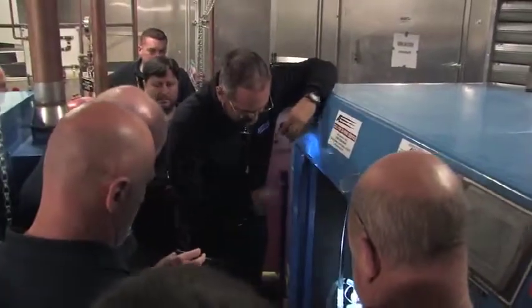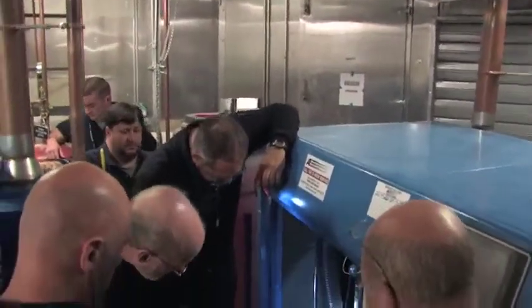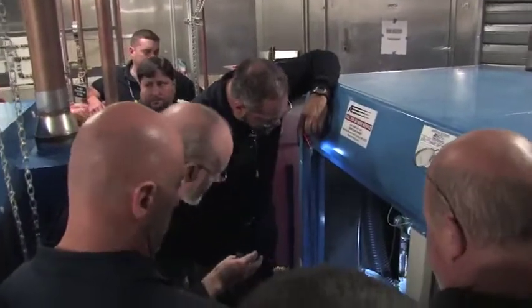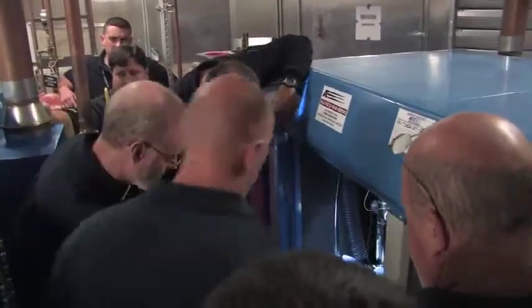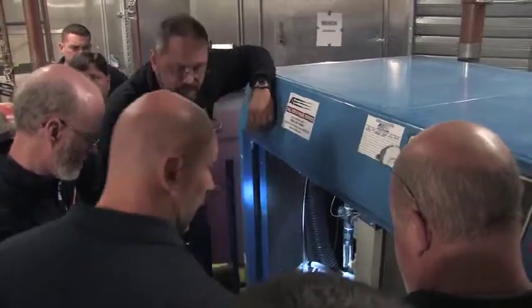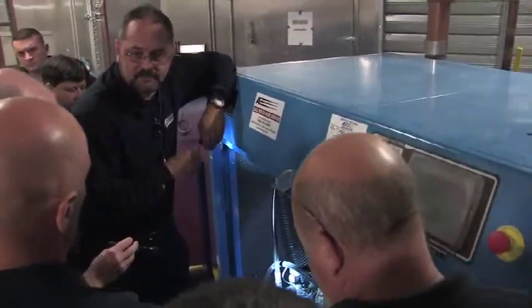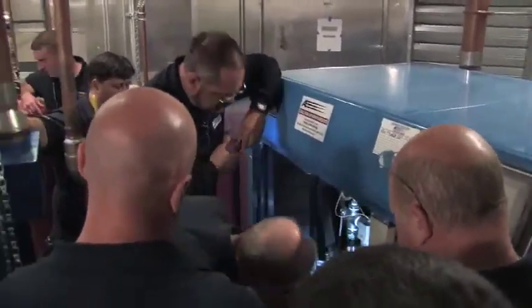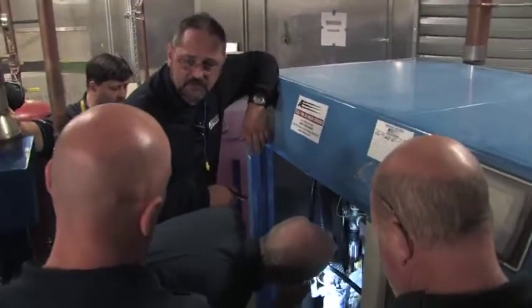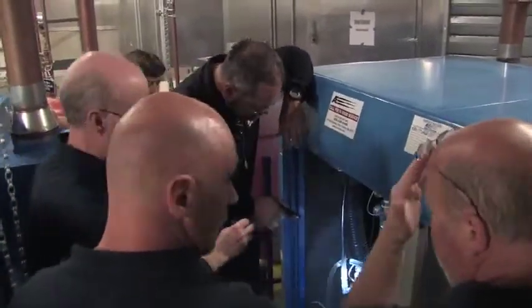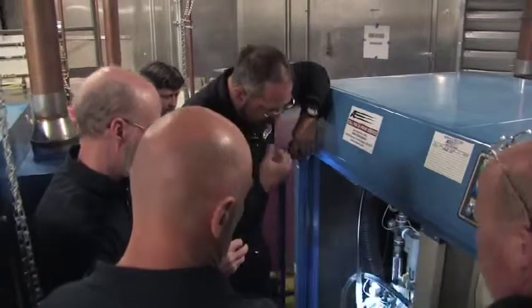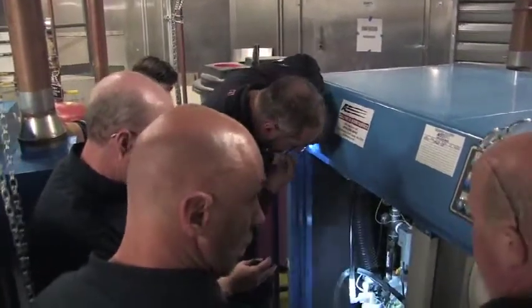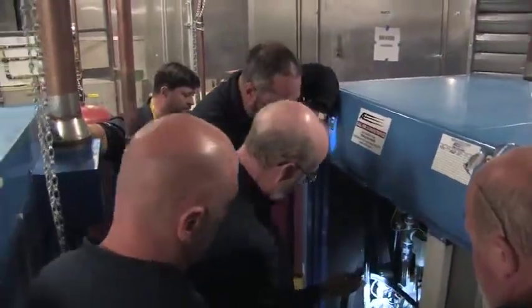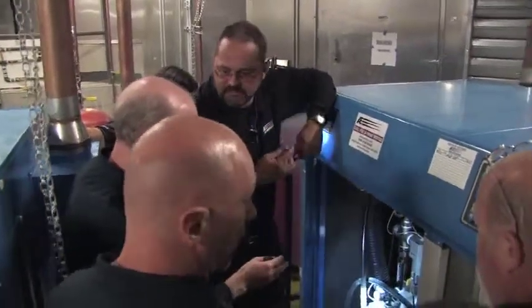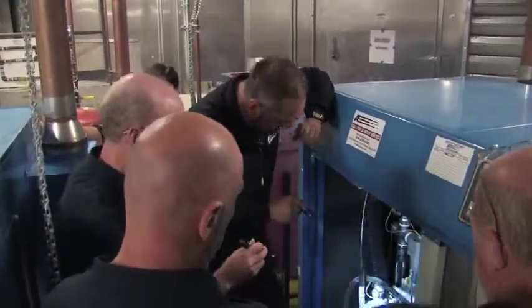Is that new? I've not seen that. They've been on there for a few years now. I guess it's not. Yeah, we don't have this on the ones over across the way. Yeah, it's probably been 3 years, 4 years. Those are about 5, 6 years old now, I think. Yeah. That pressure drop, can that pressure drop be seen up on the screen too? No. It's got wires on it. They do? It's a signal. There's a switch inside it. If the differential gets too high, it goes in as a fault, and it'll tell you. Yep. Yep.